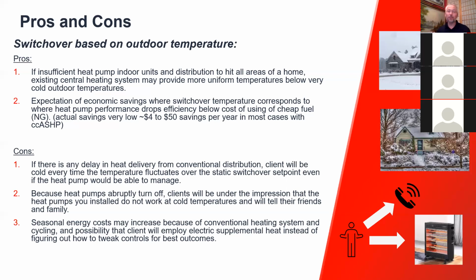It doesn't matter how well you describe it to one person or two people, but after a year or two, they're going to forget it. They're going to be like, oh my gosh, this heating system is really weird. We get this kind of change. Then all of a sudden, we get below a certain temperature and the heat pump doesn't work. Apparently, they would think heat pumps don't work below that temperature because they'll forget that it's actually programmed into the system to have that swap over. So not only do you create a real sensible comfort problem, but you also create this impression that heat pumps don't operate at colder temperatures, even while it's just the strategy that's employed for integrated controls.